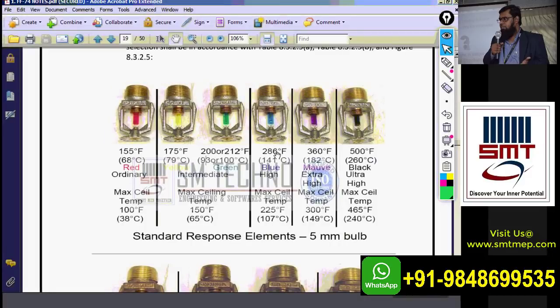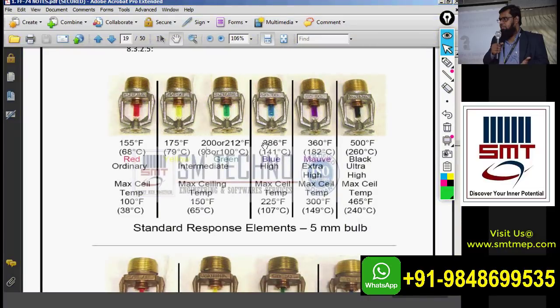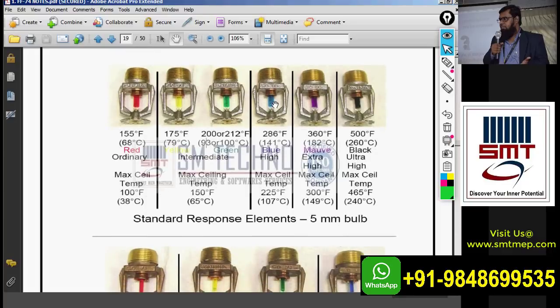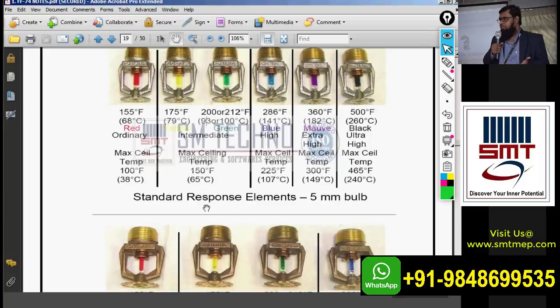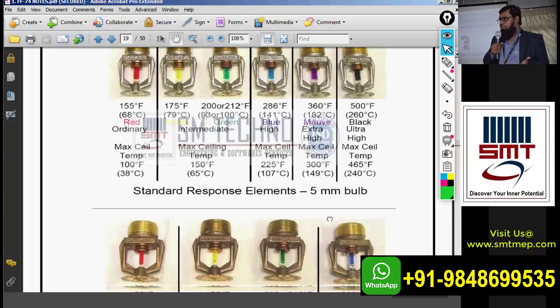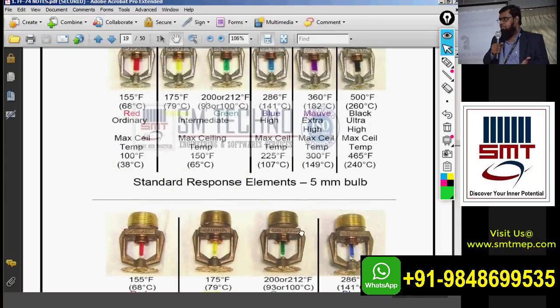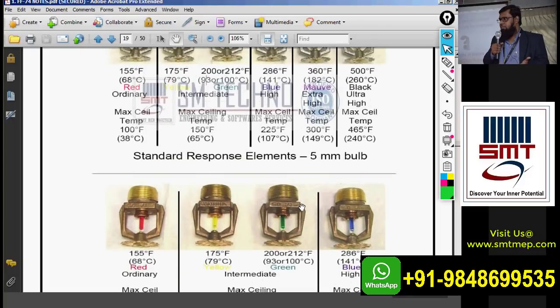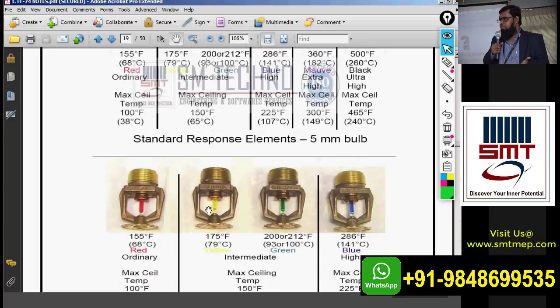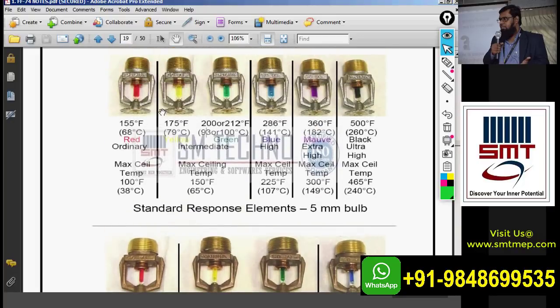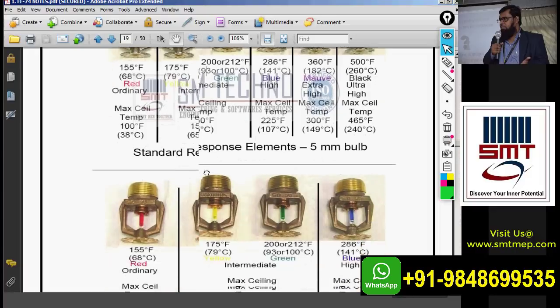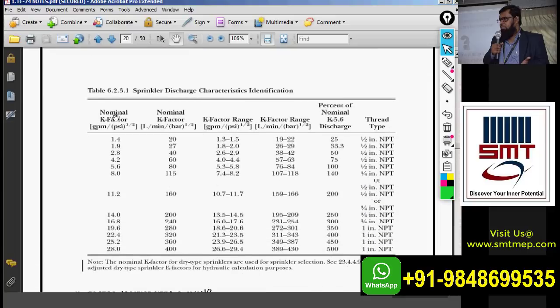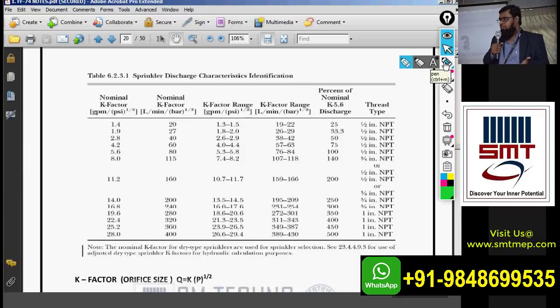As per construction we know pendant, upright, sidewall, and open type sprinklers. As per the diameter of the bulb, sprinklers are also classified: standard response uses a 5 mm bulb, and quick response uses a 3 mm bulb. The bulb contains a liquid — alcohol or another liquid depending on the manufacturer — which expands as per the thermal rating.